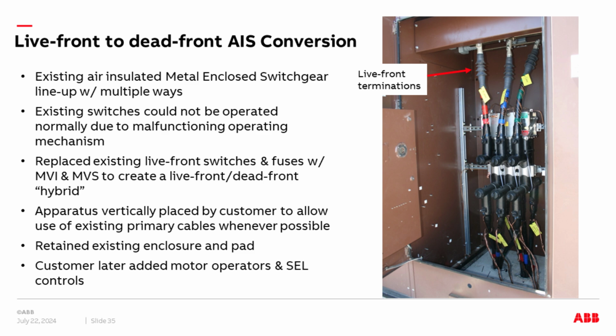Another example of modularity, this solution here, the customer wanted to go from a live front to a dead front application. So you can see in the top right, these gray live front terminations connected to the incoming bus, and then the cable runs down into a 600 amp elbow, so it's a shielded dead front connection. And then the vacuum bottles are inside the rubber behind these metallic brackets, and then you have the outgoing cables at the bottom, also dead front 600 amp cables, T-bodies.